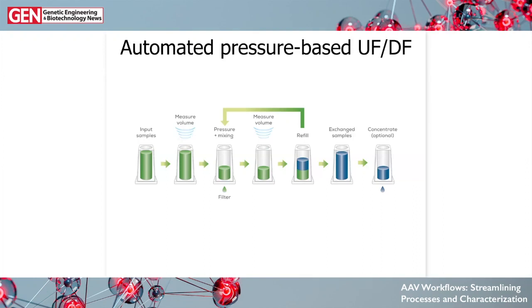BigTuna will measure the volume using a non-contact ultrasonic volume sensor, then begins the buffer exchange process where it uses positive pressure to push sample down through the bottom of the membrane. Critically, it also uses orbital mixing so that we don't have over-concentration at the membrane, and everything stays in solution and well-mixed. At the end of one positive pressure cycle, BigTuna measures the volume again, figures out how much buffer passed through the membrane, and refills with the new buffer. Repeat that cycle until you have 95 or 99 percent exchange, and optionally concentrate your sample up higher at the end.